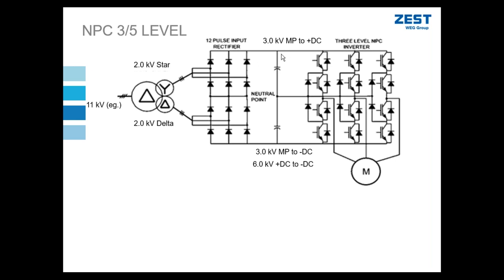And then my series rectifier supplies my DC link that is split by a neutral point. Because I introduce this neutral point, what happens is this, if I measure the voltage from the neutral point to the positive DC link, I would get, so I'm supplying 2 kV from my secondary, but because it's going through my diodes, I need to multiply that by 1.35 approximately. So that would give me 3 kV if I measure from neutral point to positive DC link voltage.